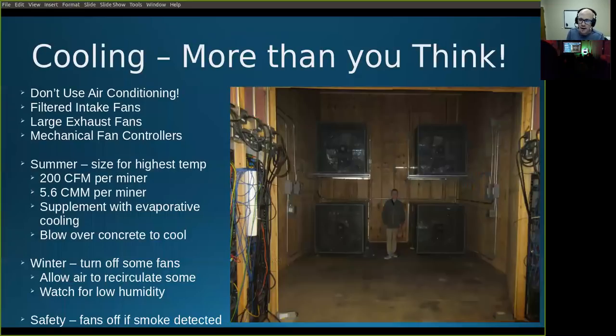All right, cooling - I tell people, put in more than you think you need. Well, you all are in Winnipeg, so maybe it's not that hot in summer, but we size it for what we need here in Georgia, which gets to 95 to 100 degrees Fahrenheit in summer. Each of these fans in the picture moves 20,000 cubic feet per minute - I guess I want to convert that to cubic meters per minute, what do I do, divide by 40?